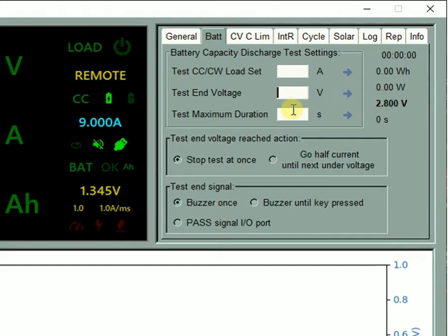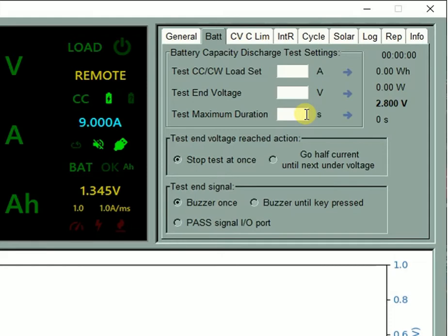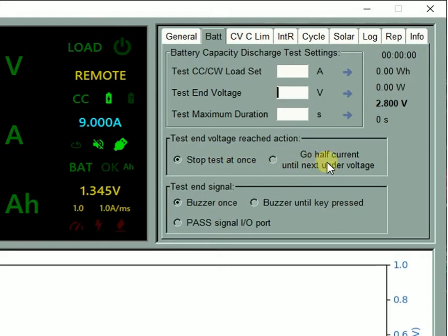You may optionally define a maximum test duration in seconds for safety reasons. Use zero to disable it. Choose your preferred action when the test end voltage is reached: end the test at once or switch to half of the programmed test current value until the next undervoltage condition occurs.